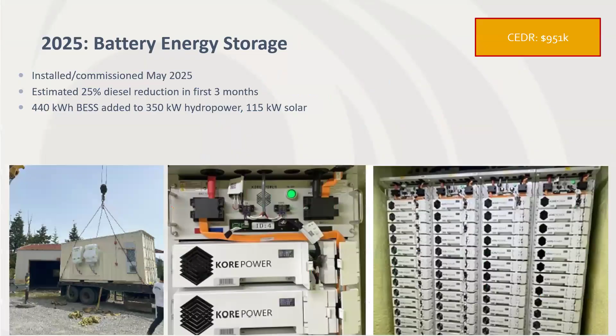It's estimated to have a 25% diesel reduction in the first three months. The main reason it saves diesel is, for one, you no longer have to run diesel in the background in case your load suddenly peaks above what solar and hydropower can provide. Because of that, the idling in the background can really quiet down, and you can cycle-charge your generators—running them at peak efficiency, then turning them off while the battery takes over, going back and forth.